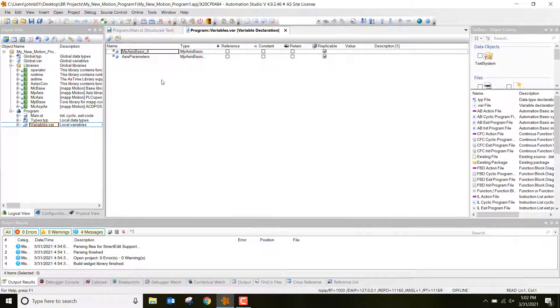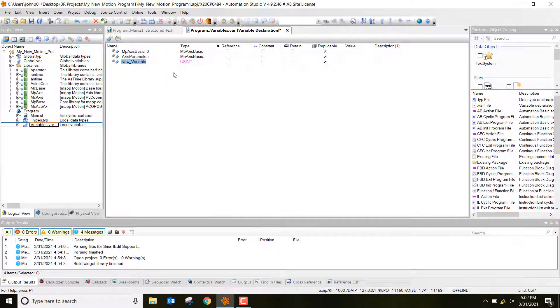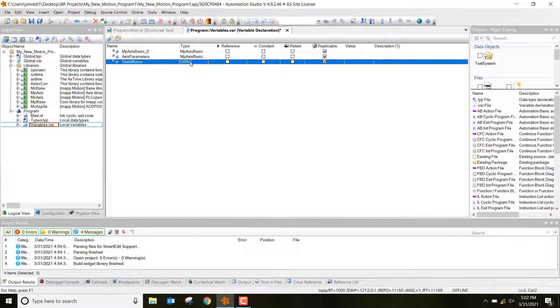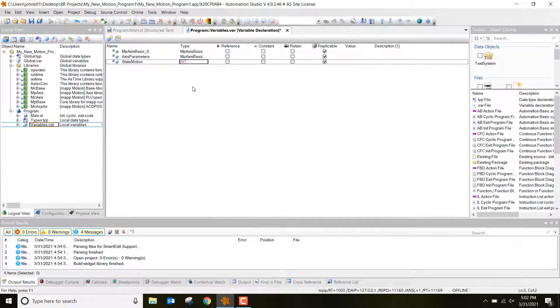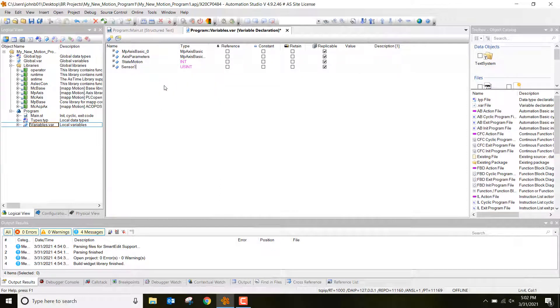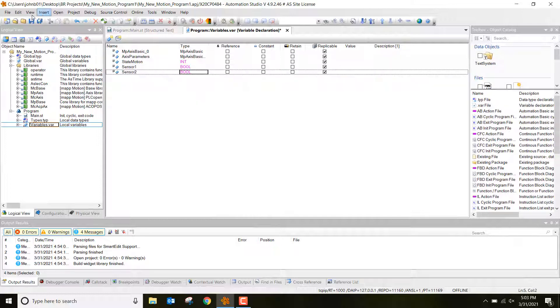What I want to do is add a couple of new variables. Since we're going to do a case statement today, I'm going to make a new variable which is an integer and name it state_motion. Right-click in the white space, click Add Variable, name it state_motion, set the type to INT, and hit Enter. Then I'm going to add two more variables for our sensors — those are the booleans we've used before. Add variable sensor_one as a boolean, and add variable sensor_two as a boolean. Then hit Save All and close out.